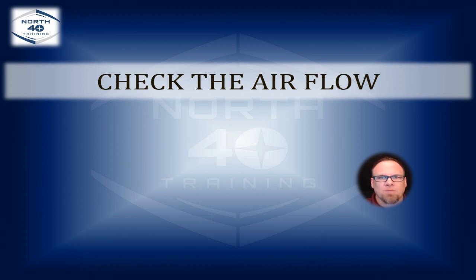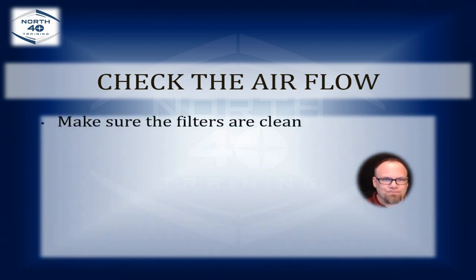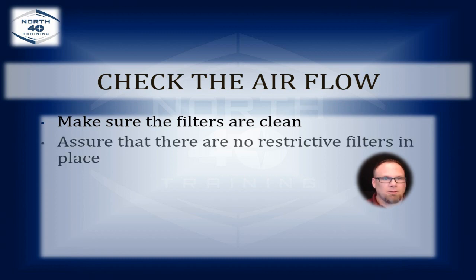So in looking at airflow, there's a couple of things you got to think about. First of all, you've got to make sure that the filters are correct. They've got to be the correct filter for the application, the correct size for the application. If either of those things are wrong, it doesn't matter where you have things set, you may not have the proper airflow no matter how you look at it. You've got to make sure that the filters aren't too restrictive.